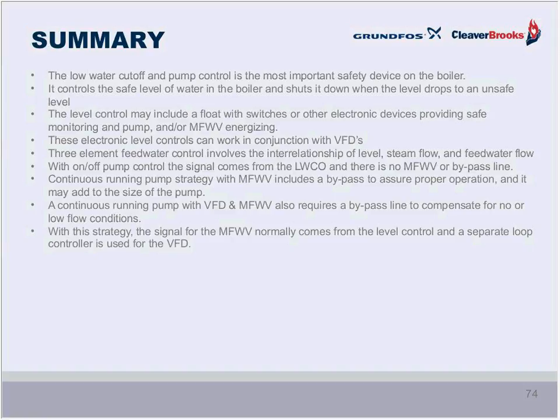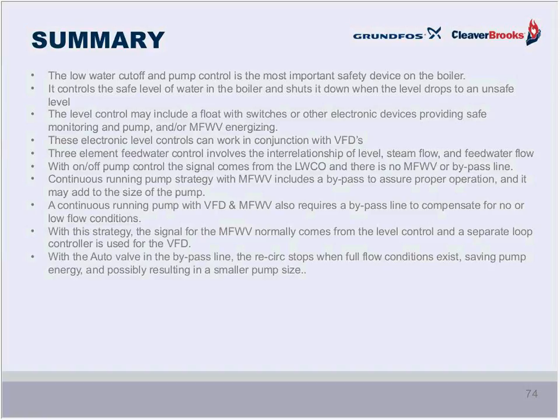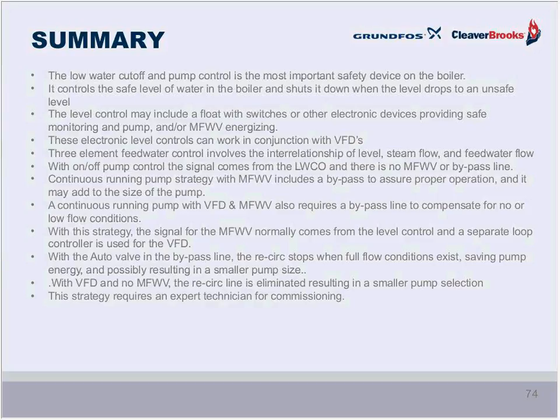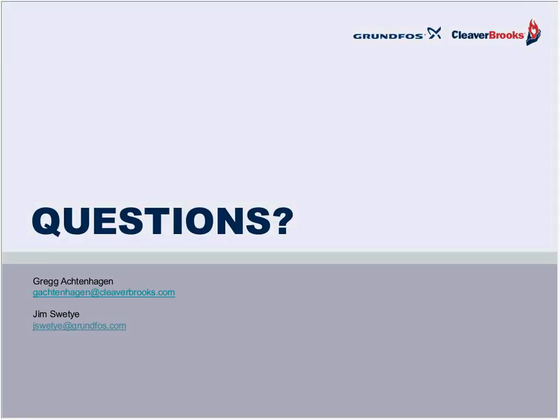With this strategy, the signal for the modulating feedwater valve normally comes from the level control, and a separate loop controller is used for the VFD. With the auto valve in the bypass line, the recirc stops when full flow conditions exist, saving pump energy and possibly resulting in a smaller pump size. With the variable frequency drive and no modulating feedwater valve, the recirc line is eliminated, resulting in a smaller pump selection. And this strategy requires an expert technician for commissioning. I think that Jim emphasized that correctly.